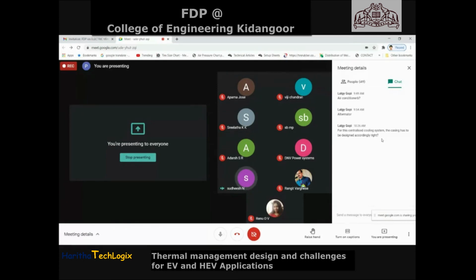Sir, is there any integral coolant pump in that arrangement? Normally in an engine we have a coolant pump. Yes, we will have a coolant pump. Both of them, they just mentioned it as coolant pump, and it will be placed at different locations also - either near the battery one coolant pump will be there, and near the DC-DC converter, depending upon the pressure requirement. Because if the overall thermal loop is very long, it will automatically lose pressure and the flow velocity will be reduced. So depending on the flow velocity requirement, there might be one or more coolant pumps needed.